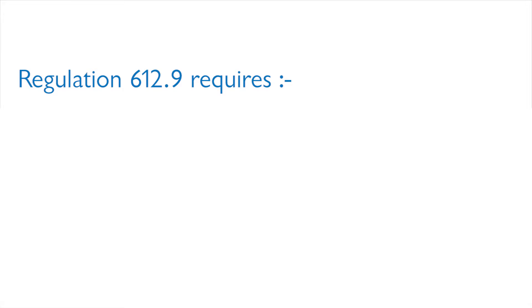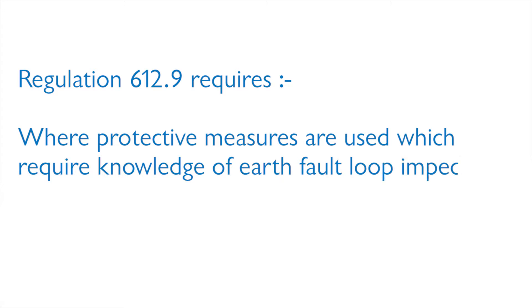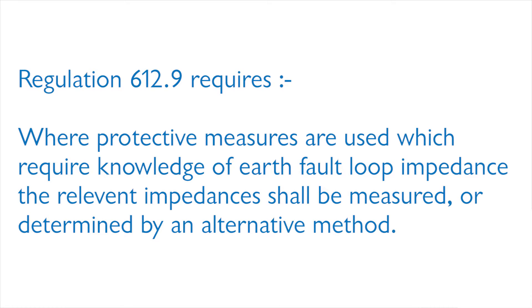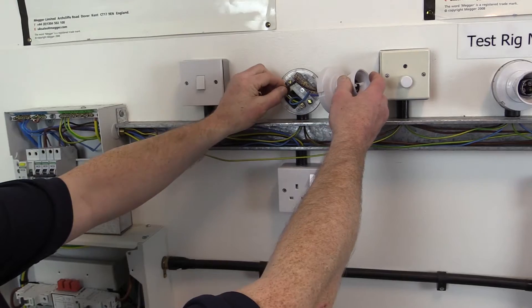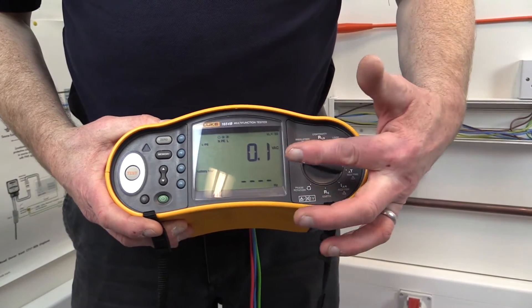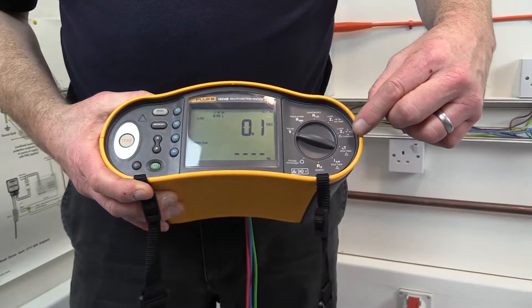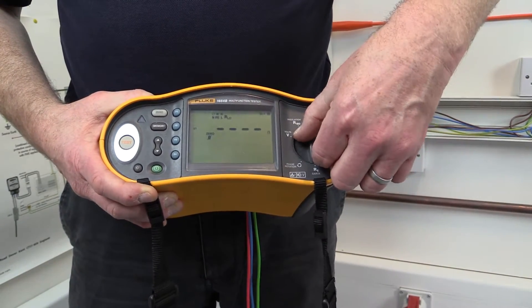Regulation 612.9 requires that, where protective measures are used which require knowledge of earth fault loop impedance, the relevant impedances shall be measured or determined by an alternative method. The earth fault loop impedance ZS will require to be determined at the furthest point of each circuit, and this can be done by using an earth fault loop impedance test instrument or a multi-function test instrument set to the appropriate earth fault loop impedance setting.